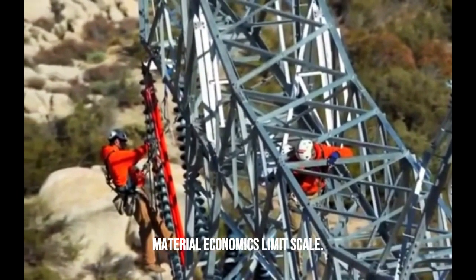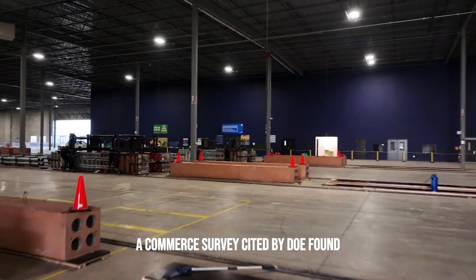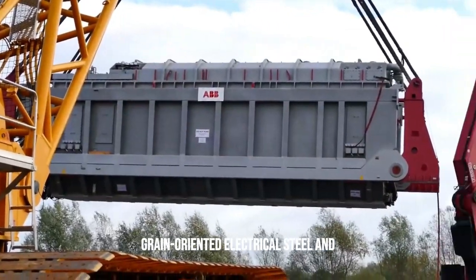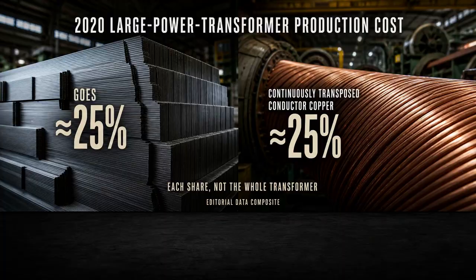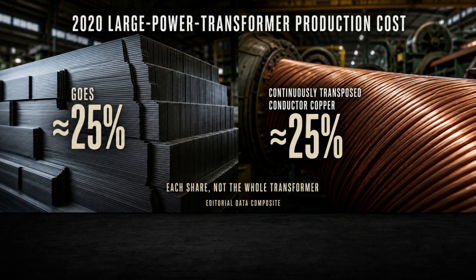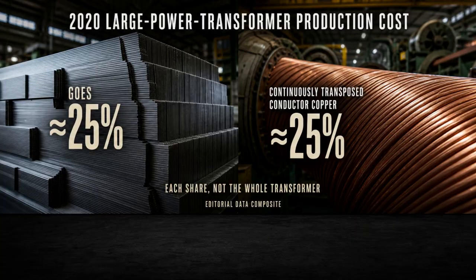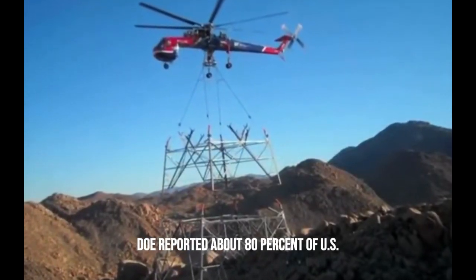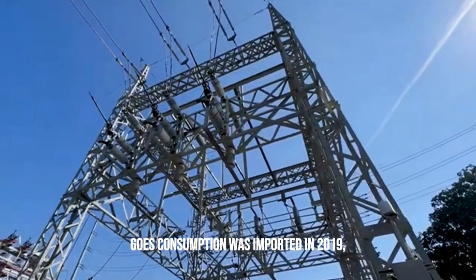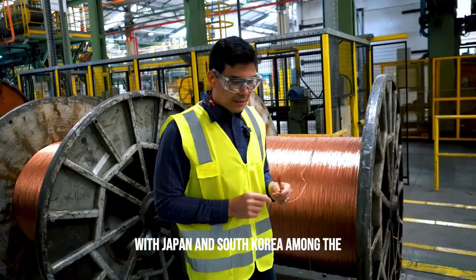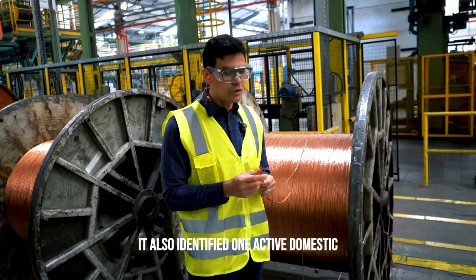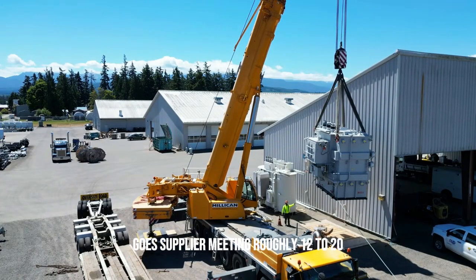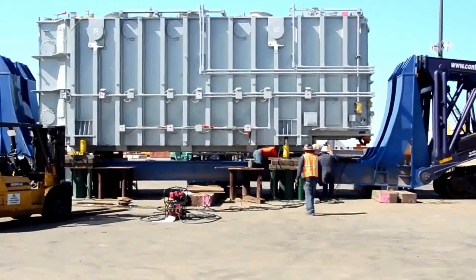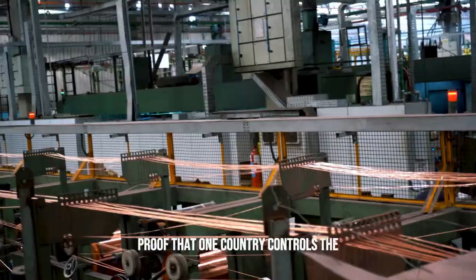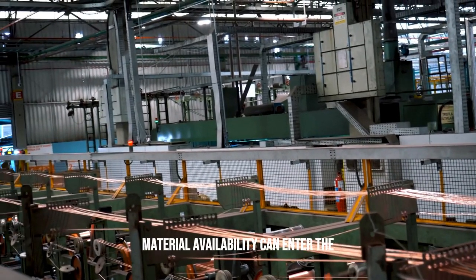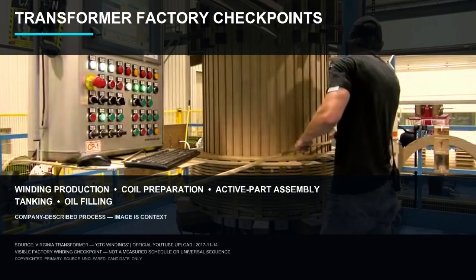Material economics limits scale. A commerce survey cited by DOE found grain-oriented electrical steel and continuously transposed conductor copper each represented about 25% of final large power transformer cost in 2020. DOE reported about 80% of U.S. GOES consumption was imported in 2019, with Japan and South Korea among the sources. It also identified one active domestic GOES supplier meeting roughly 12 to 20% of demand. Those are dated supply pictures, not proof that one country controls the chain. Material availability can enter the qualification schedule at the factory.